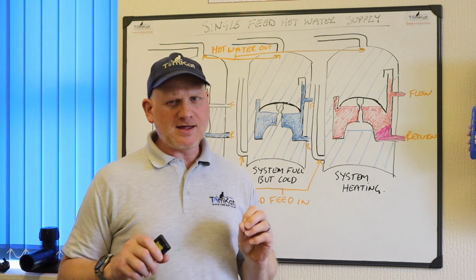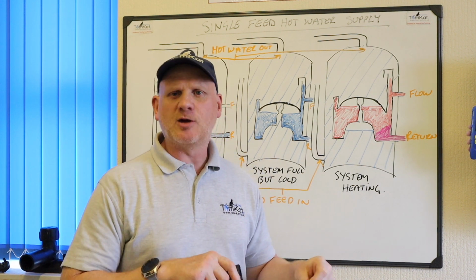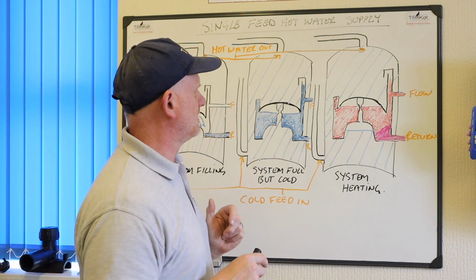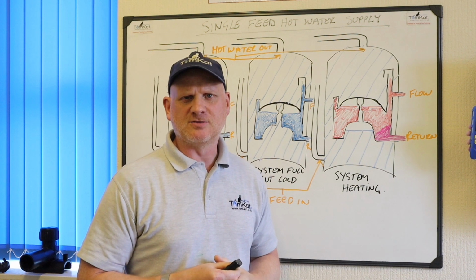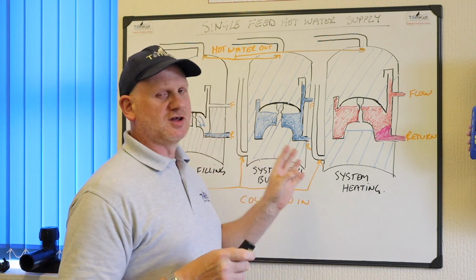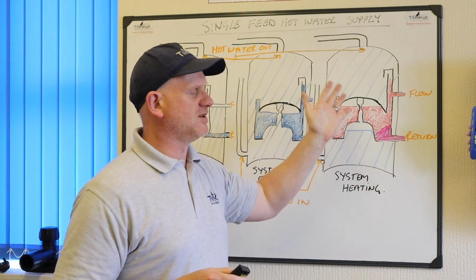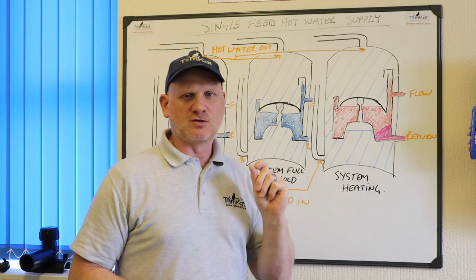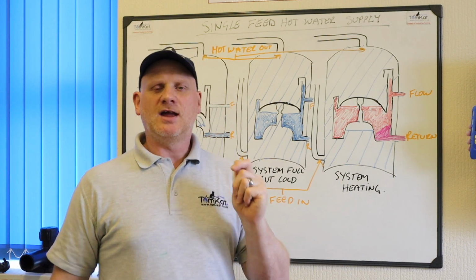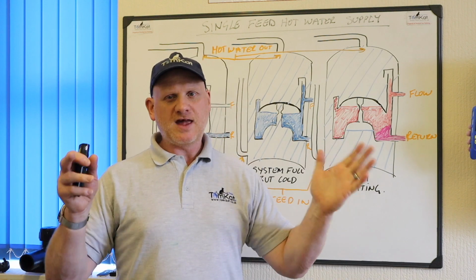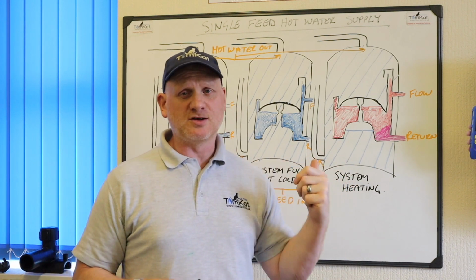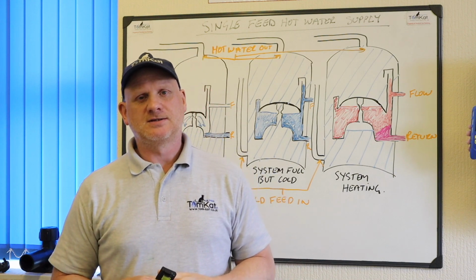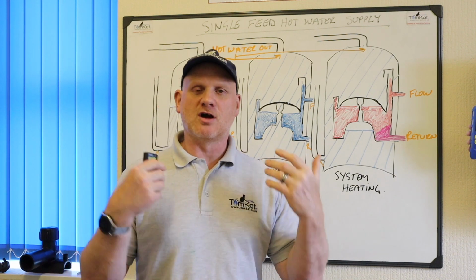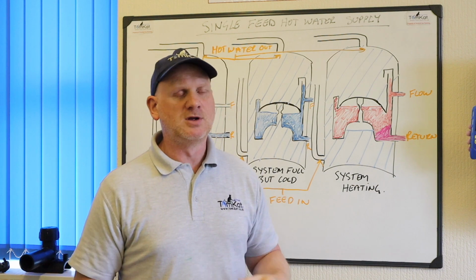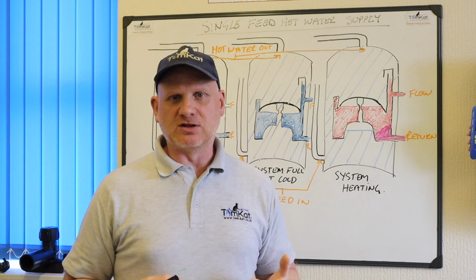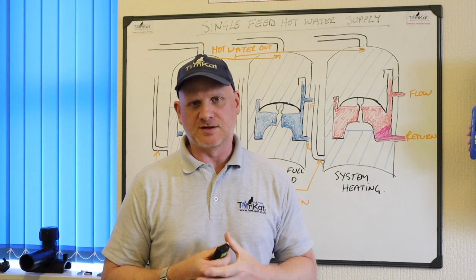Now basically what it is, it's an indirect cylinder, but it's installed as if it's a direct cylinder, because there's no F&E system. Okay, so the water from this feed system feeding the hot water is also the same water which goes into the central heating system. So there's our first problem. With these old systems, we couldn't put inhibitor in there. There's no way we can put any cleaning chemicals or any protection chemicals in the system, because it'll mix when you initially fill the system with the hot water cylinder.